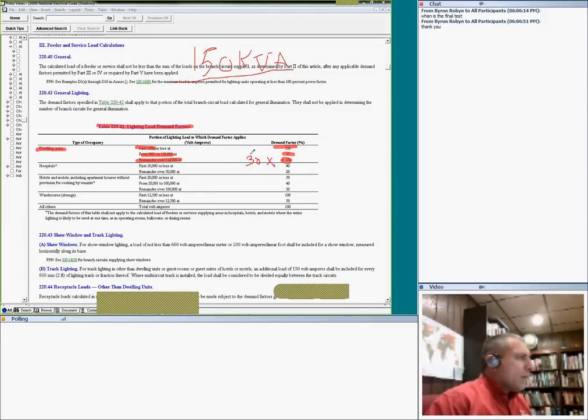And between 3 all the way to 120, that will give you 117K. Multiply these by 35 percent, and the 3K, leave alone. And add them all up. So 3K, multiply by 100 percent; up to 117, multiply by 35 percent, which is 0.35; and anything higher than 120, multiply by 0.25. And then find the demand. We talk about the demand load for a dwelling unit.